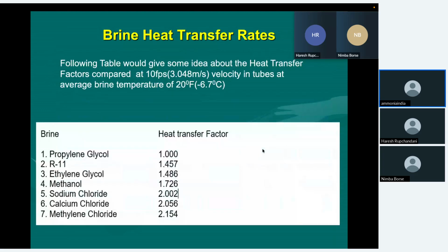The next slides will show you heat transfer coefficient comparisons of various refrigerants. Propylene glycol has only one, whereas R11 ethylene glycol has nearly 40% more heat transfer coefficient. Therefore, ethylene glycol is more popular. Methanol water, sodium chloride, and calcium chloride all have much higher heat transfer coefficients. This propylene glycol is one.